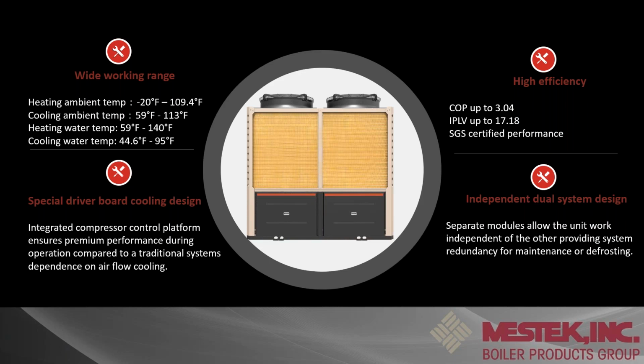On the efficiency side, when it comes to heat pumps, everything's driven off of COP, which I'll explain on the next slide. But this other particular rating here, the IPLV, is an integrated part load value. Because it is an inverter compressor modulating just like a high turn down boiler, they look at those inner parts of that load and calculate the efficiency as a total.